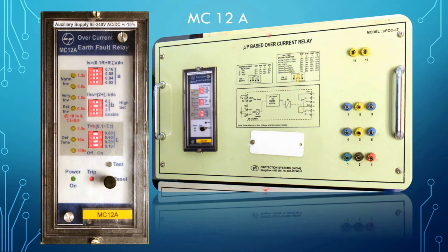Whatever the characteristic set, according to the characteristic, the relay will operate if the current crosses IS. But if the current crosses IHS, then it will not bother about whatever characteristic you have set. It will trip instantly. So this is the relay's internal protection, the instantaneous relay. That means this relay can handle overcurrent faults as well as instantaneous tripping.